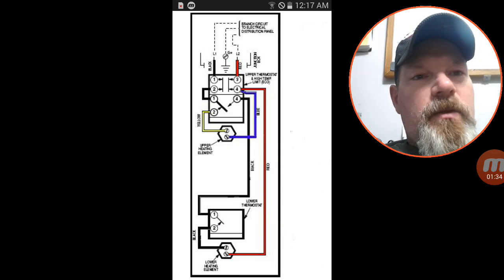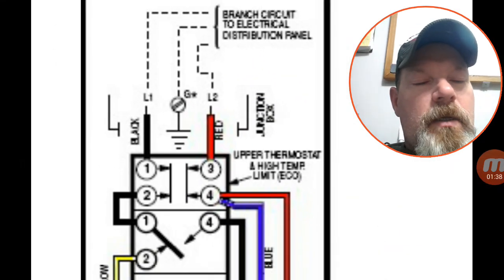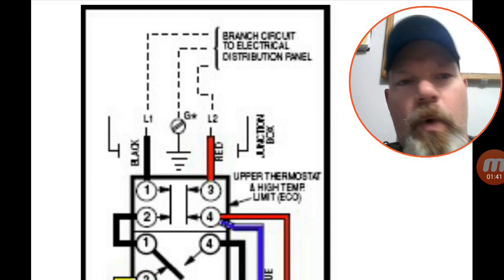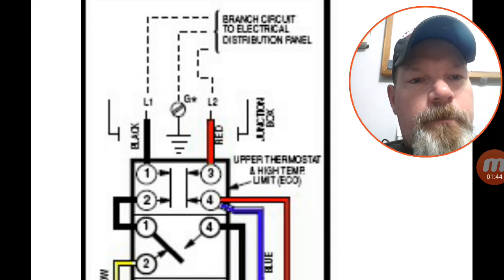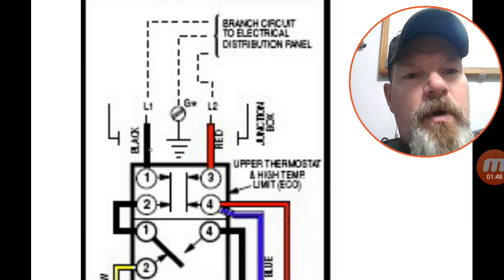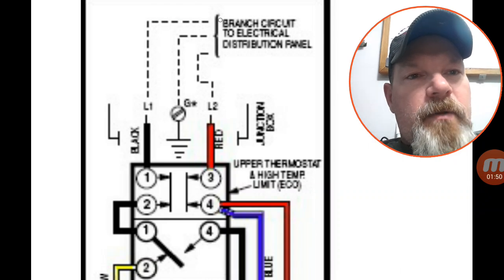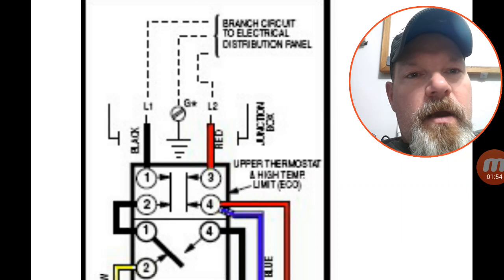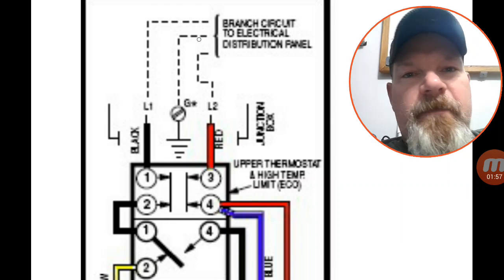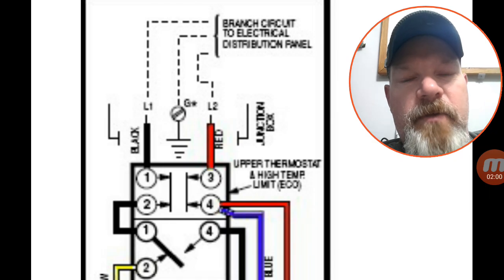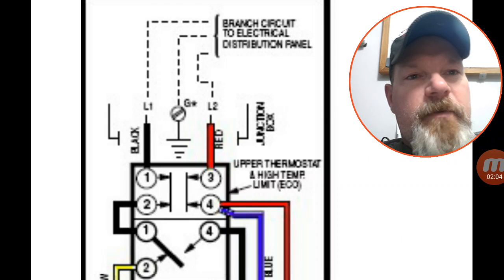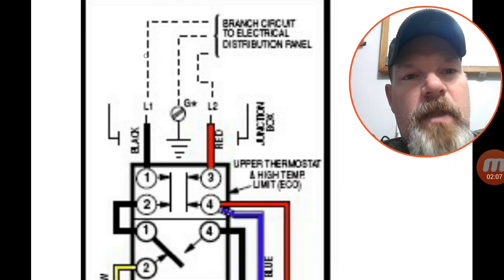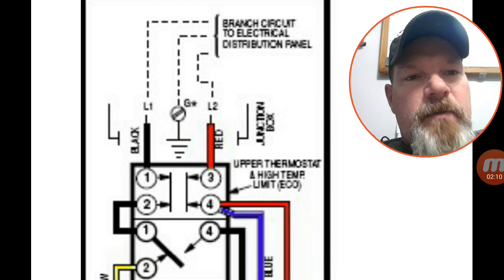So let's get into the wire here real quick. We're going to start at the top, take this one wire at a time and explain what's going on and how it's all working. We're going to start with L1, that's the black wire. Up here, this is your wire coming into the water heater, typically fed from your panel, your fuse block. You've got two 120 volt legs which give you your 240.